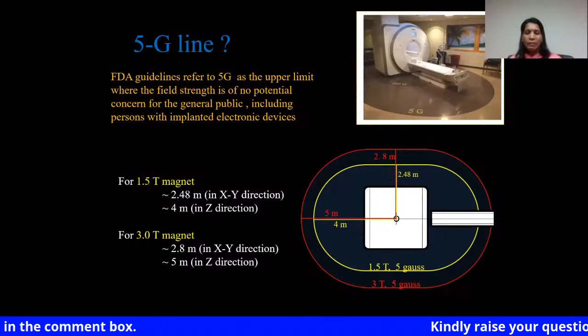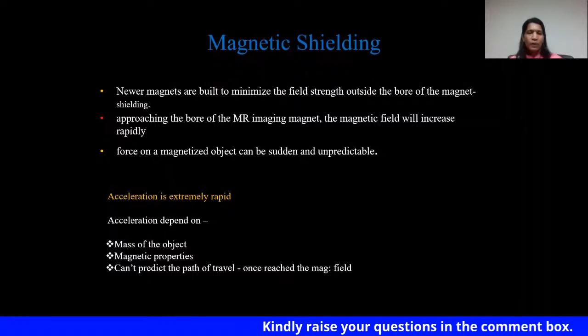And the 5 Gauss line extension depends upon the strength of the magnetic field. For 1.5 Tesla, it will be 4 meters, and for 3 Tesla, it will be 5 meters. Also, the fringe field extension depends upon the magnetic shielding. Shielding means we are producing an additional magnetic field by using secondary coils and limiting the flux lines to the bore. So magnetic shielding will reduce the fringe field extension, but the cost of a shielded MR system will be more. And the shielding will be different for different systems.